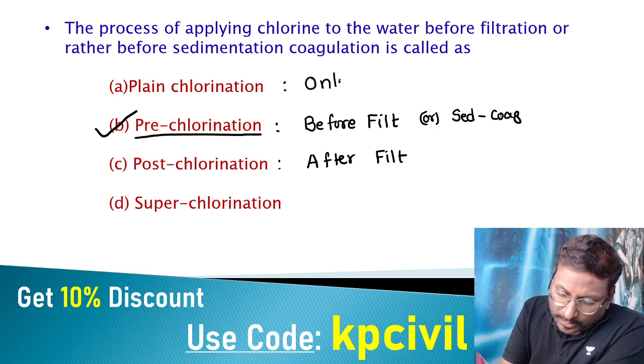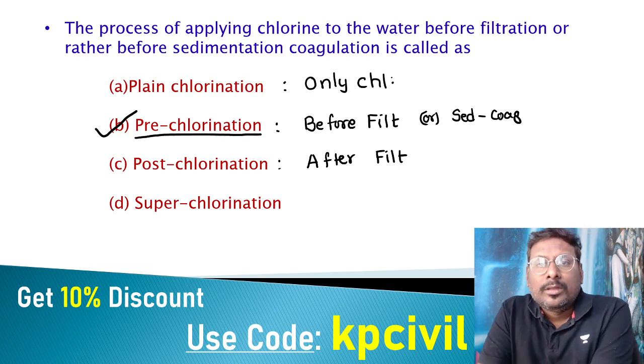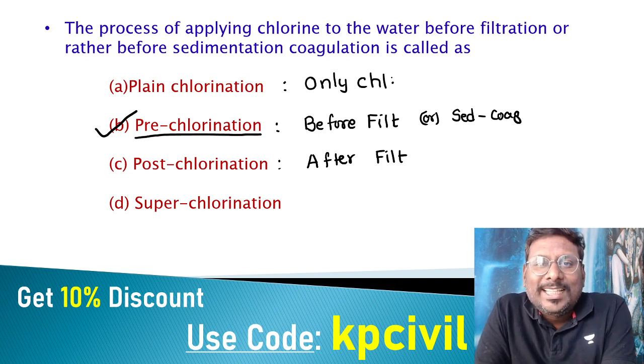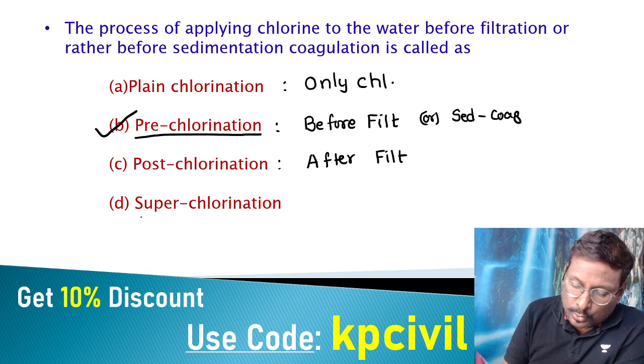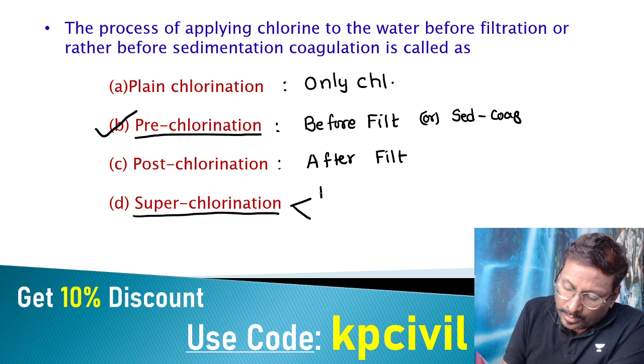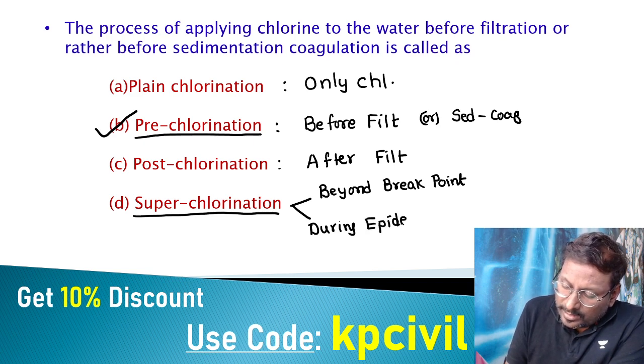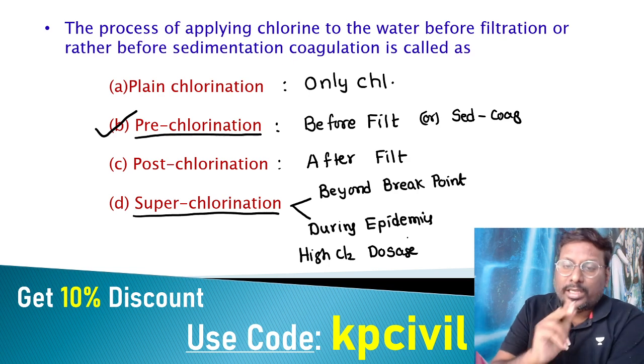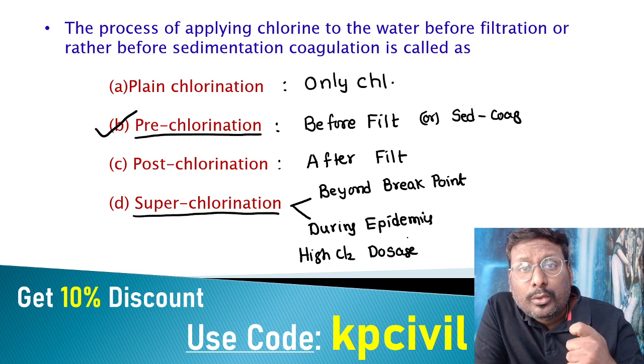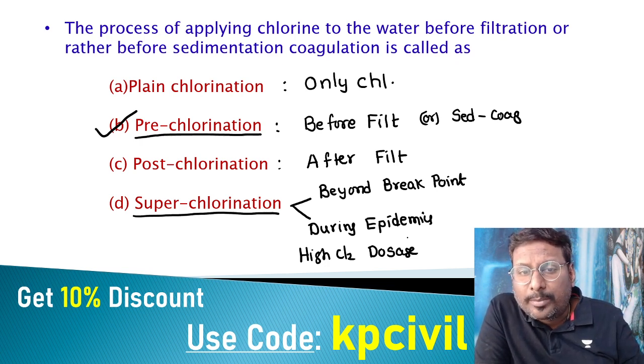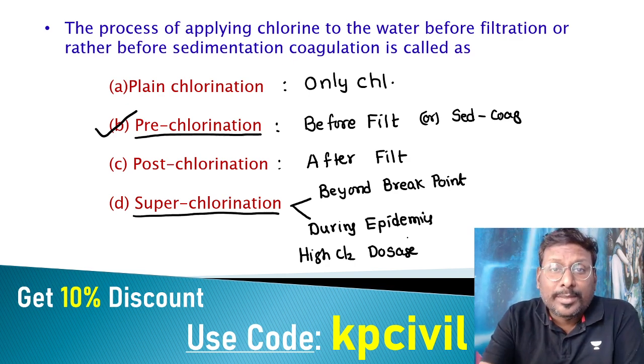If no other treatment is carried out — no filtration, no sedimentation, no coagulation, only chlorination — that is plain chlorination. Super chlorination is used under two conditions: first, addition of excess chlorine beyond the breakpoint; second, during floods or epidemics when an excess chlorine dosage is applied. Beyond breakpoint addition or very high chlorine dose during epidemics is super chlorination.